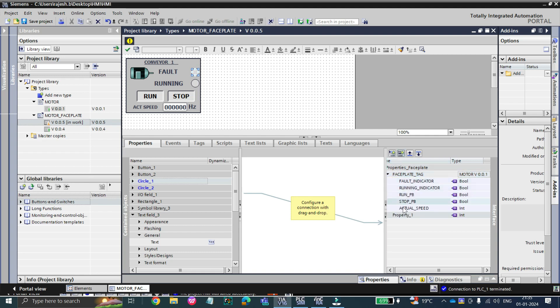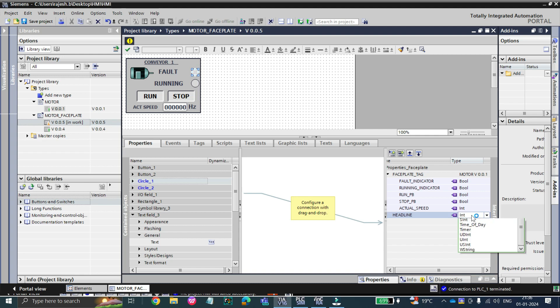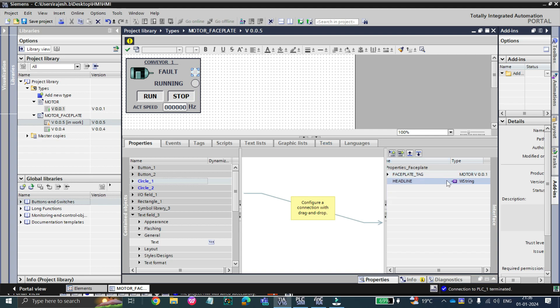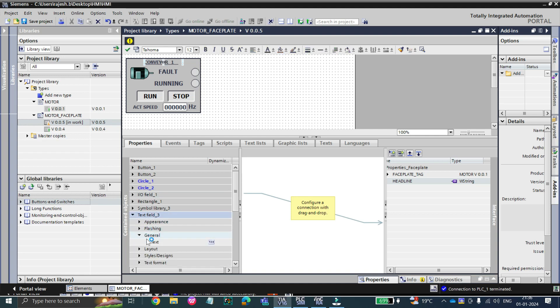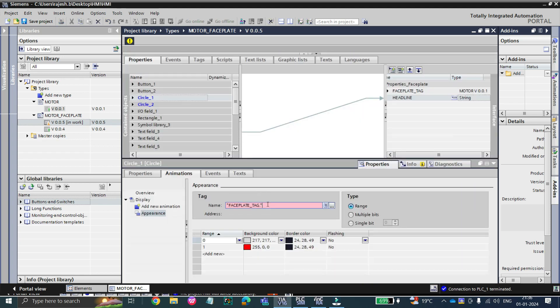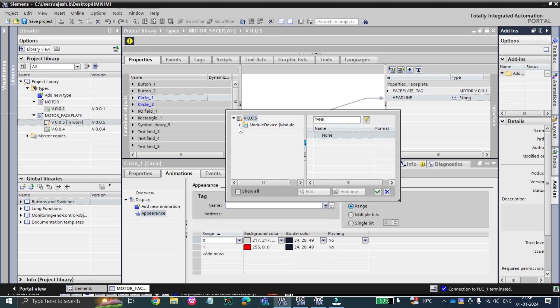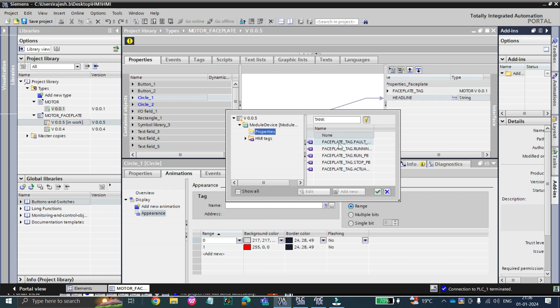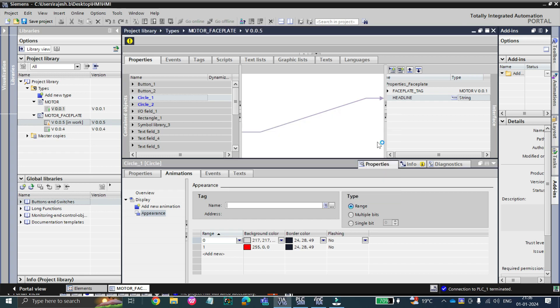We also need to add a heading or headline, since we didn't create a data type for headlines, and its data type would be string. At the outside interface, there will be only two entries: one is 'headline' and the second is 'faceplate tag'. Give the headline property 'conveyor1' — expand the text field, go to general, and drag and drop into the headline. Now the headline is connected. Next we need to add animations for all the indicators, so let's open the properties. You can see there is an error; click on the three windows, add the properties, and you can see 'faceplate tag dot fault indicator' — this is done.